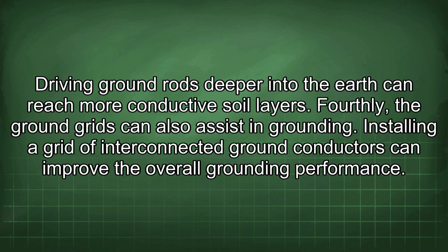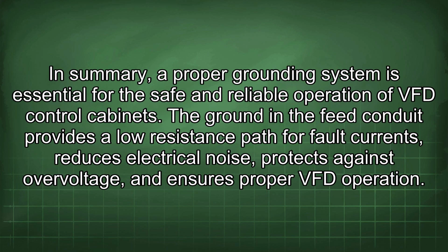Installing a grid of interconnected ground conductors can improve the overall grounding performance. In summary, a proper grounding system is essential for the safe and reliable operation of VFD control cabinets. The ground in the feed conduit provides a low resistance path for fault currents, reduces electrical noise, protects against overvoltage, and ensures proper VFD operation.